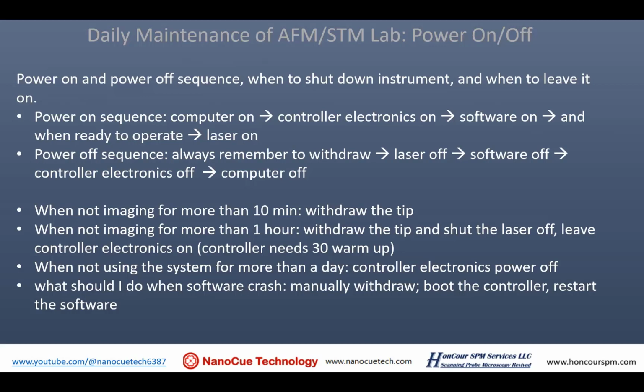If you're not scanning for an hour, you walk away a little bit, you should withdraw and then turn the laser off, because your laser has a finite lifespan. You should try not to consume its lifetime when you're not using it. And if we're not using it for a day, you could turn the controller off. And at the end, if the software crashes, first you always manually withdraw by turning the knob counterclockwise to protect your tip. Then you reboot your controller. If you have to, you restart the software and computer and so on and so forth.